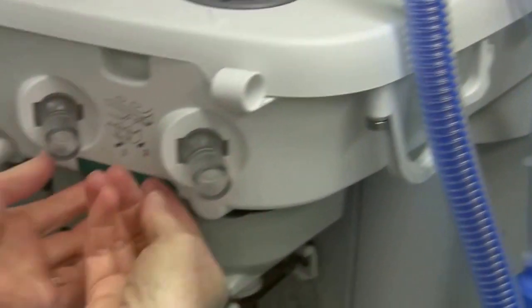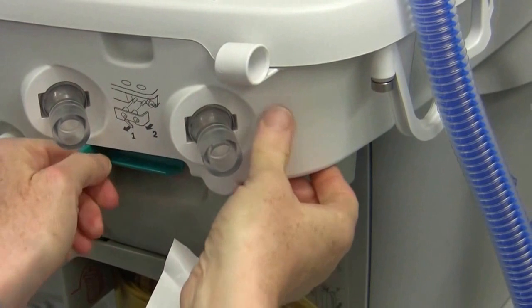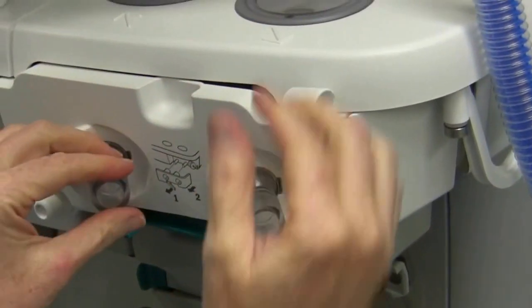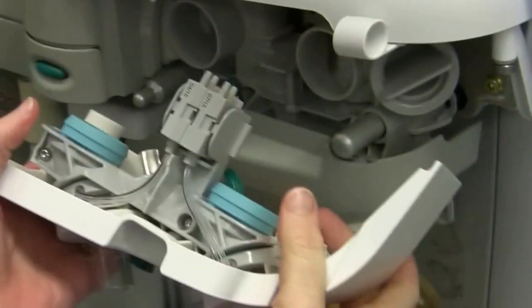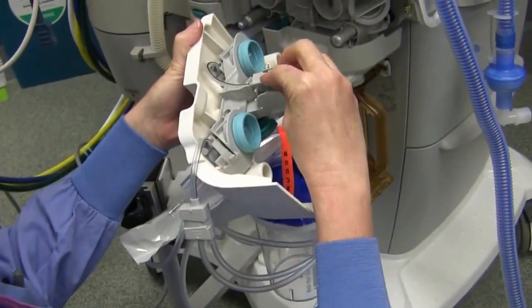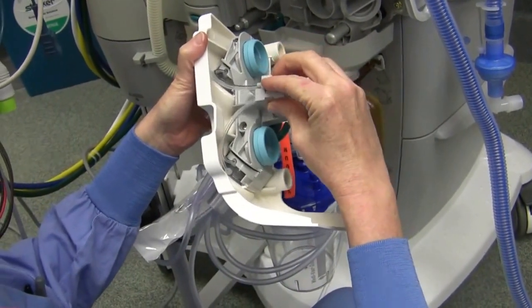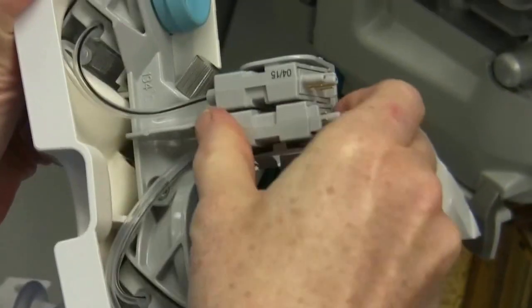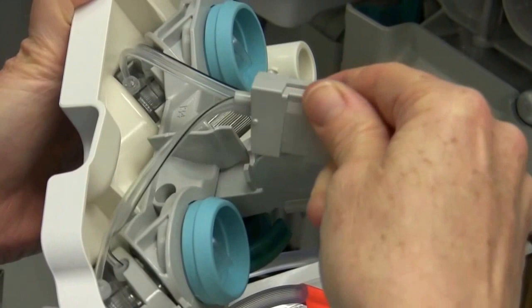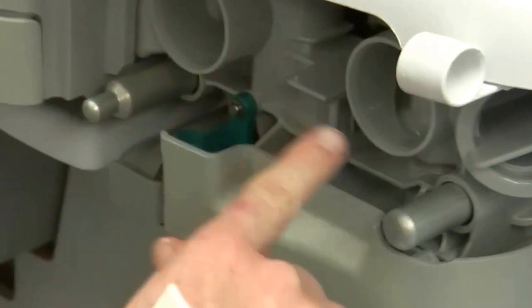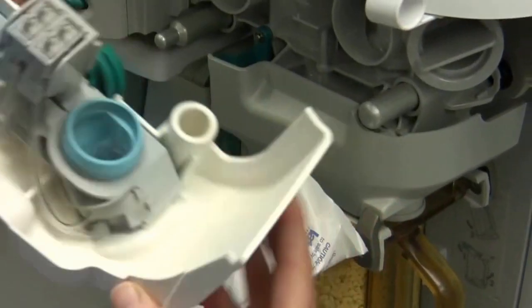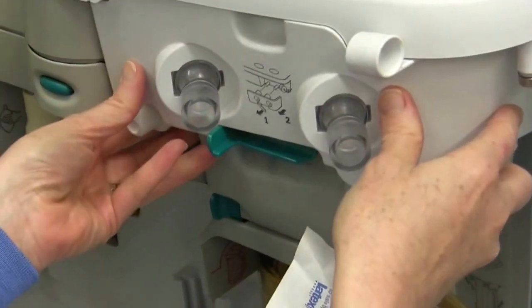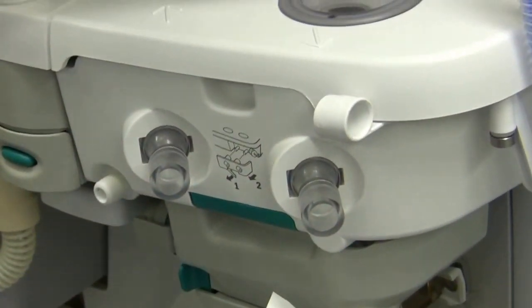If we could go back to that very first step where we needed to calibrate those flow sensors, if you take this module and shake it just a little bit like we told you to, take it out just halfway, you'll get it to read it. But many times this whole thing comes out. And with it are these modules that fall out of here. These are the flow sensors. And all you need to do if it comes apart like this, the easiest way is to put them back in together at the same time. Like that. You line up these metal pieces with these holes, and you're just going to slide it in and lock it. So don't be alarmed if the whole thing falls off.